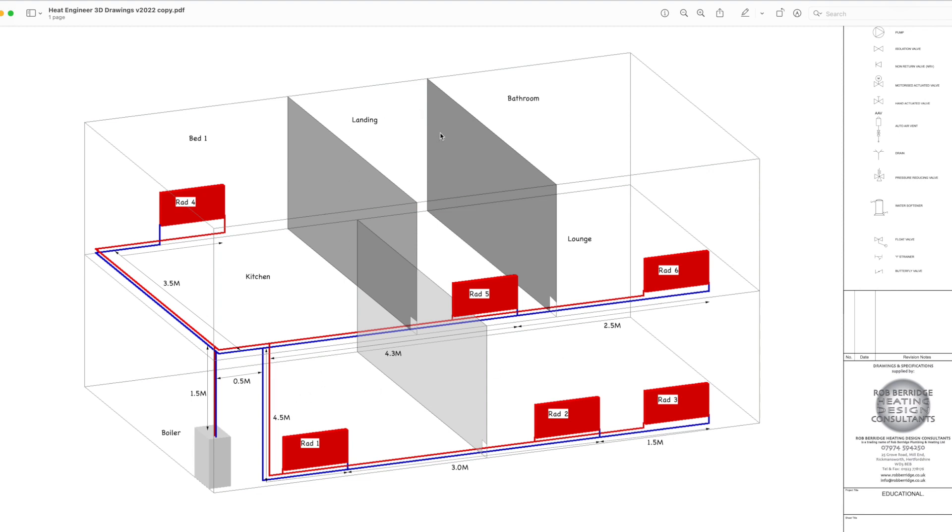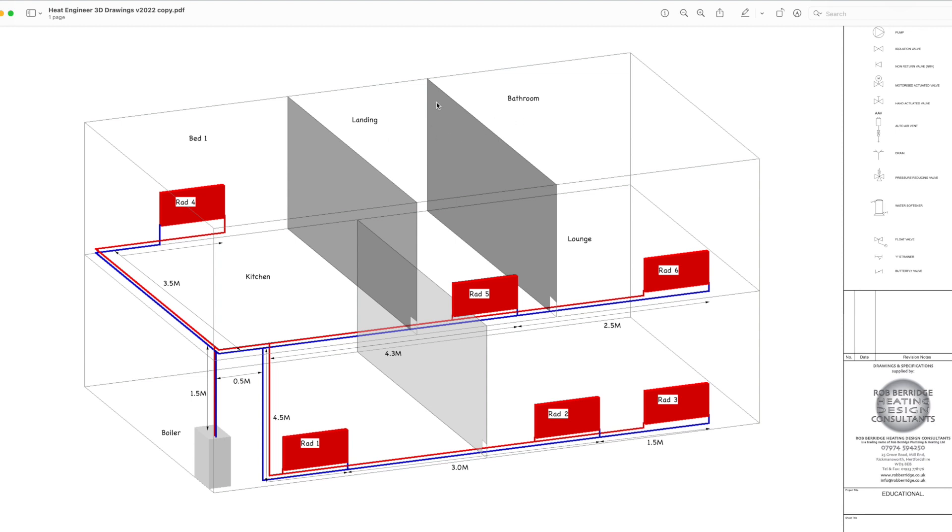So for argument's sake, this wall here between the landing and the bathroom, because bathrooms are always designed at 22 degrees and the landing is always designed at 21 degrees after the building regulations came out in 2000. And as we all know, the second law of thermodynamics means that hot will always try and go to cold, it will try to find equilibrium. So we would have to install that internal wall there, so the system knows what resistance there is between that room and that room.